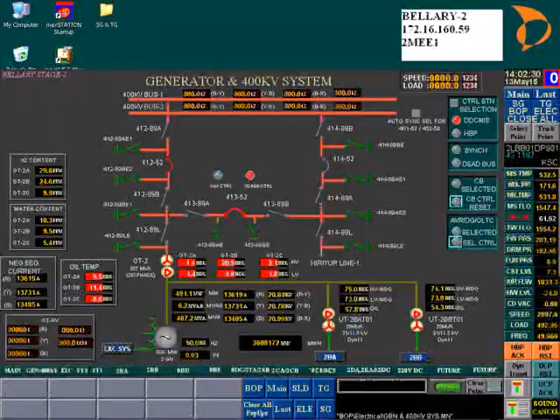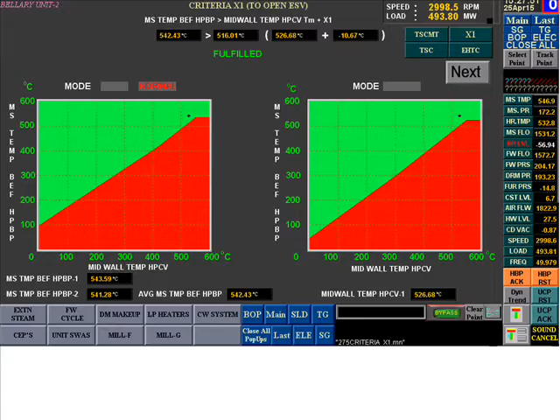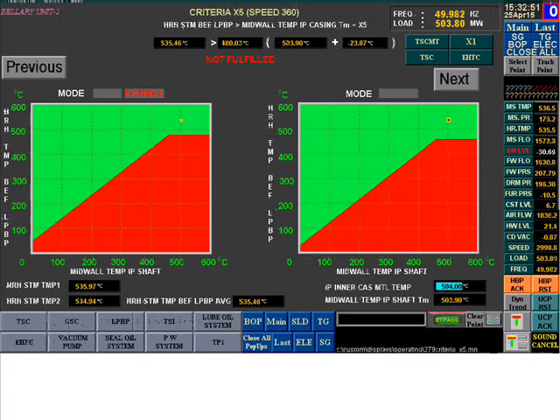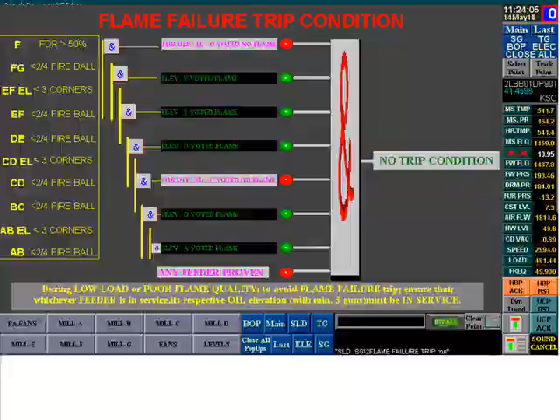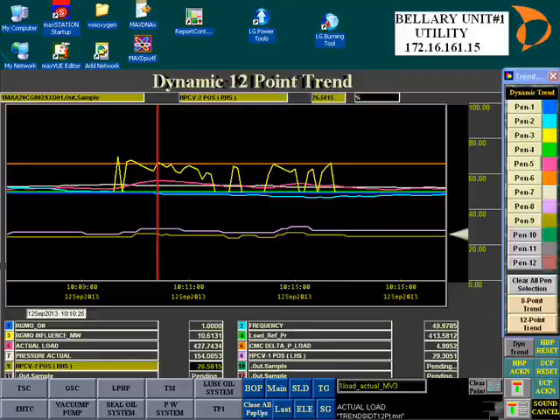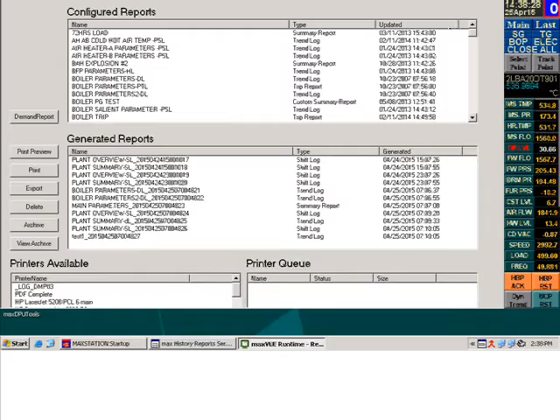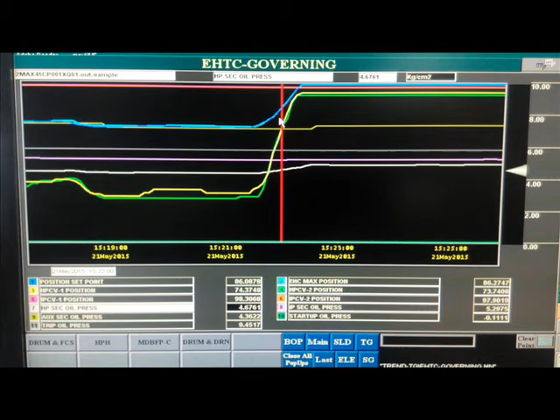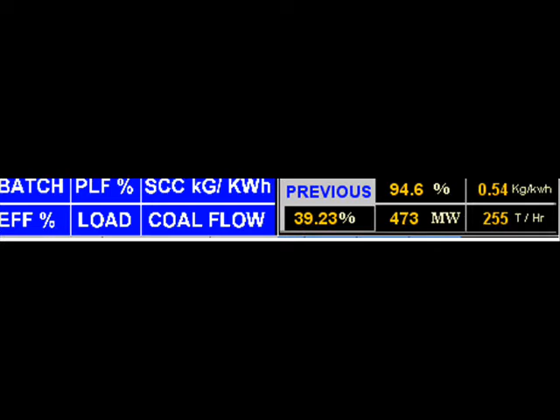Graphics designing and modifications. Testing and tweaking of control constants, and minor, to sometimes major, logic modifications in application code to the controllers. Trends, reports, and sequence of events provide a powerful executive information system to facilitate proactive decision-making and analysis of various causes of tripping, faults in the system, and parameter variations. This also provides information to share and compare present, previous, and past unit performance data over their duration of operation with the operation personnel.